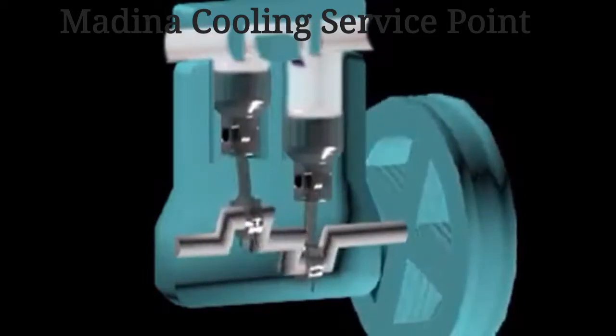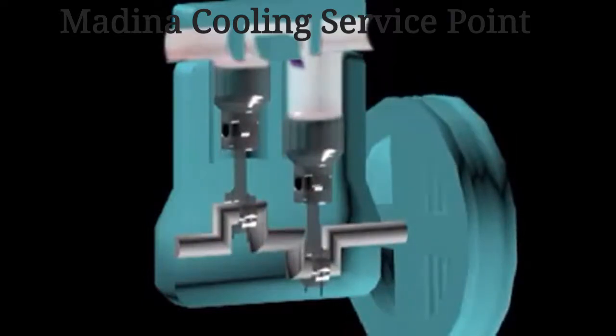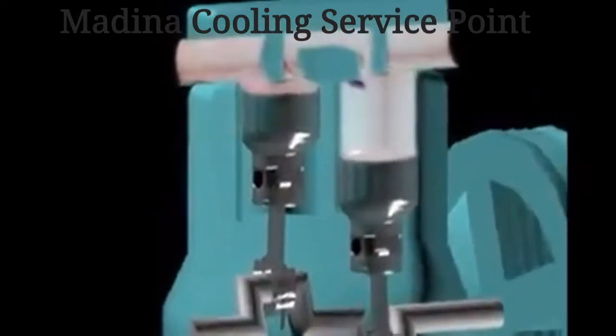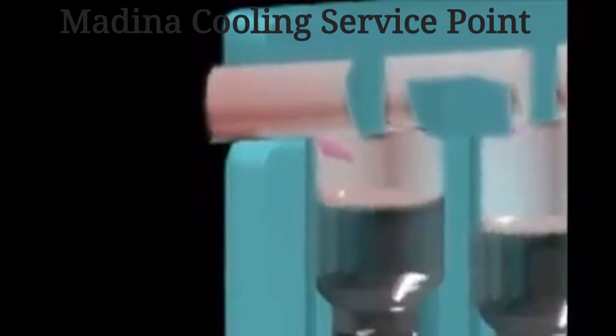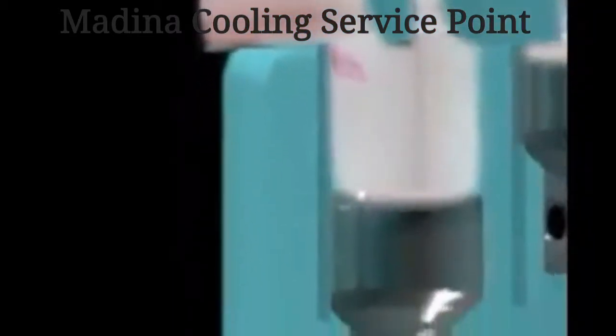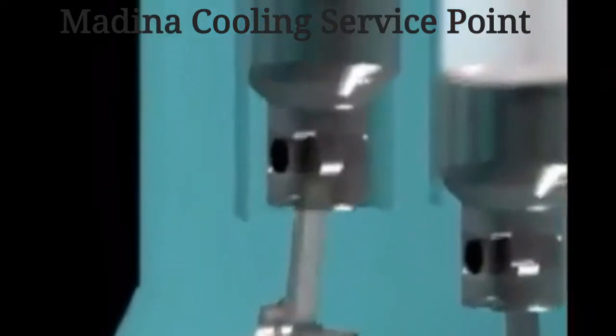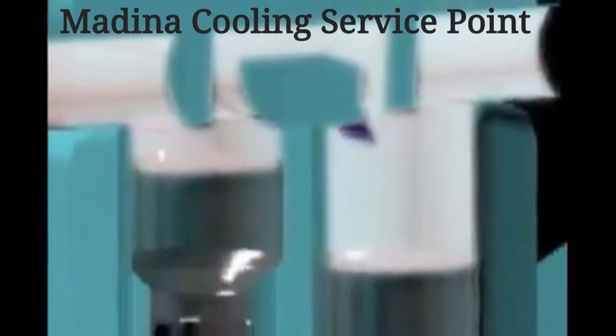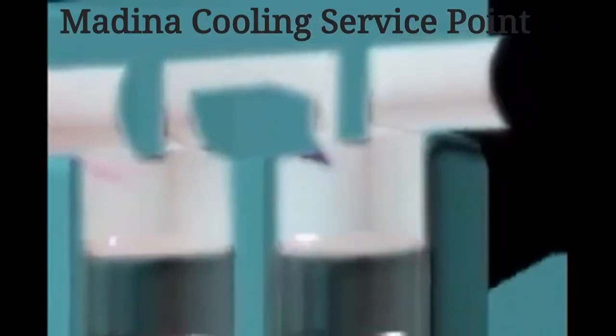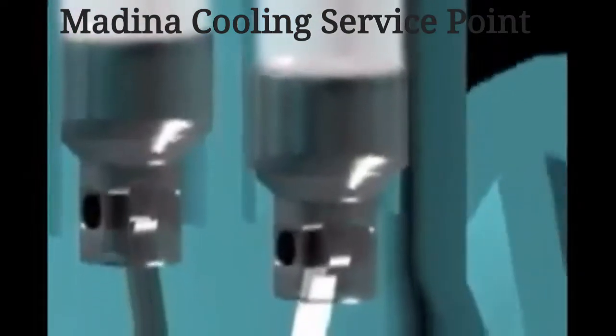The compression stroke will take place when the piston moves upward. During the stroke, the pressure rises to slightly above the discharge pressure and will cause the plate-type discharge valve to open. The refrigerant passes through at approximately constant pressure and flows to the condenser. At the end of the stroke, the differential pressure across the valve, aided by the valve spring, will close the discharge valve and another suction stroke begins.